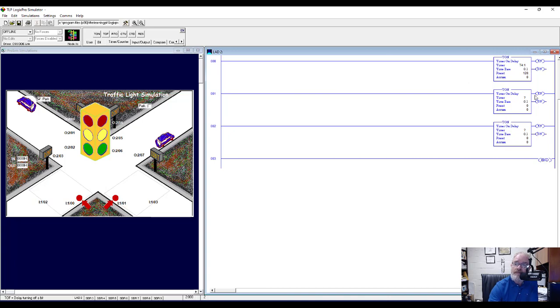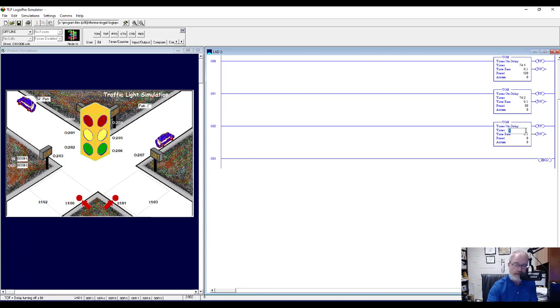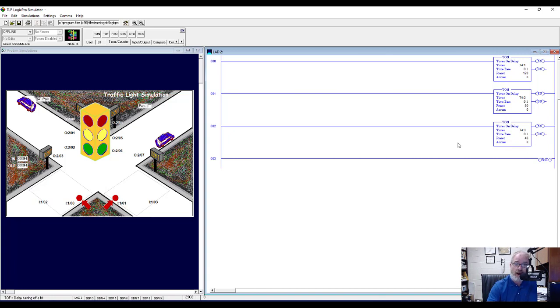The first timer is set to 120. The second timer gets address T4:2 with a preset of 80 — that's 8 seconds. Then the third one is T4:3 with a preset of 40, which is 4 seconds — 40 times 0.1 gives the 4 seconds we need. So we've got three timers: a 12-second, an 8-second, and a 4-second. Right now if we ran the program, all three would time simultaneously — that's not what we want.